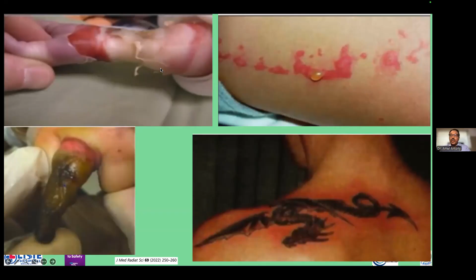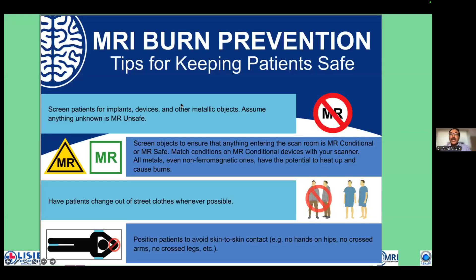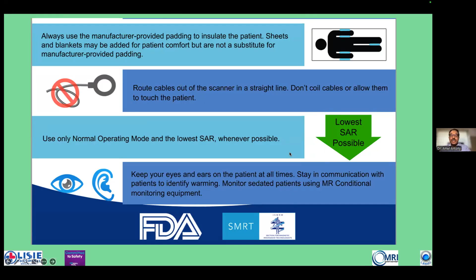Now, these are some of the examples of various types of burns which can occur. So that is a tattoo with burns. That is, again, radio frequency burns there. And burns prevention, we have already said how we can change the patient into separate clothing, avoid skin-to-skin contact, avoid contact with the inner part of the gantry, see to it that cables are routed out of the scanner, and that too in a straight line, and always use the lowest SAR possible for that particular examination, and keep the eyes and ears always protected.